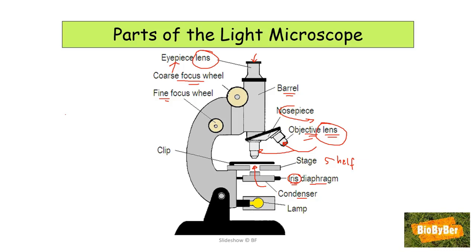The coarse focus wheel can be used to bring the specimen roughly into focus. To fine-tune the image and make it less blurry, one has to use the fine focus wheel. The condenser helps to focus the light from the mirror or the bulb up through the hole in the stage and up through the specimen. You can control the amount of light that comes through the stage by means of a lever called an iris diaphragm. The iris diaphragm links in with the iris of the eye, which controls the amount of light entering the eye — similarly, the iris diaphragm controls the amount of light going up through the specimen.